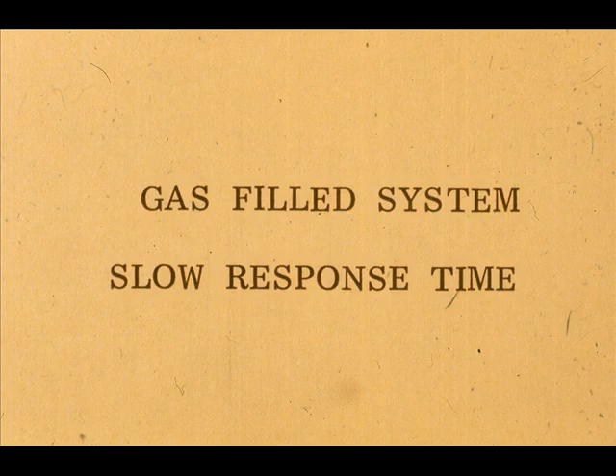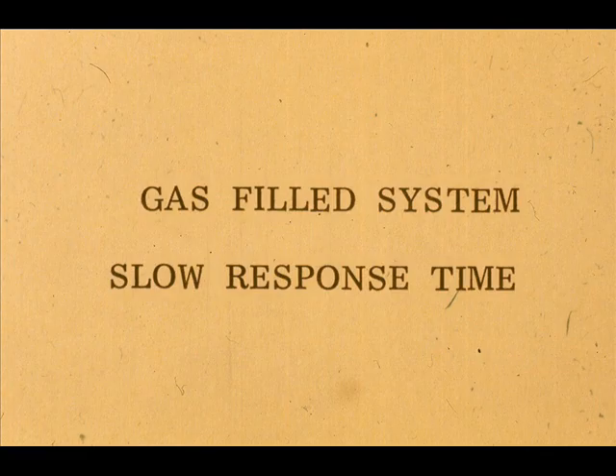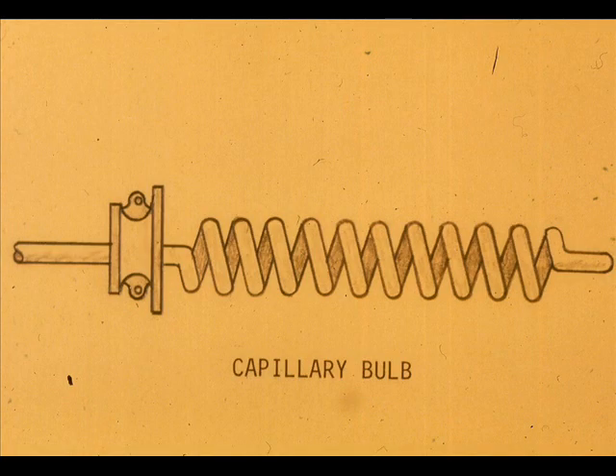Because of the large bulb, the gas-filled system has a slow response time. Sometimes a capillary bulb is used for faster response. This will not affect the accuracy because the gas-filled system measures average temperature just as the liquid-filled systems do.